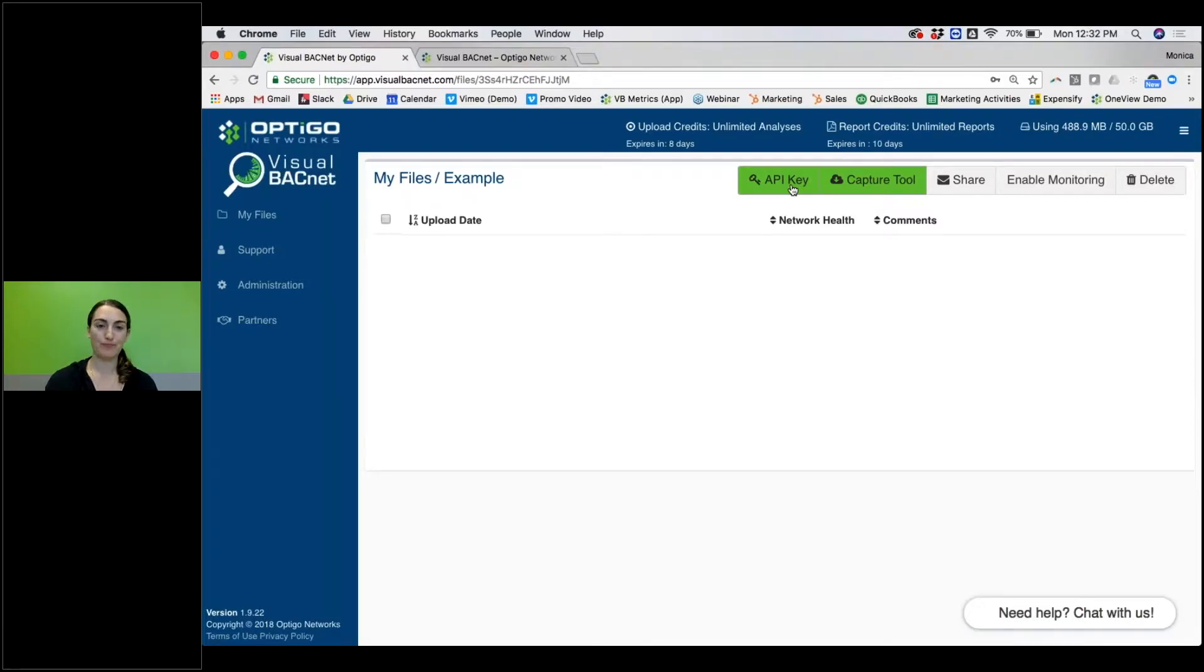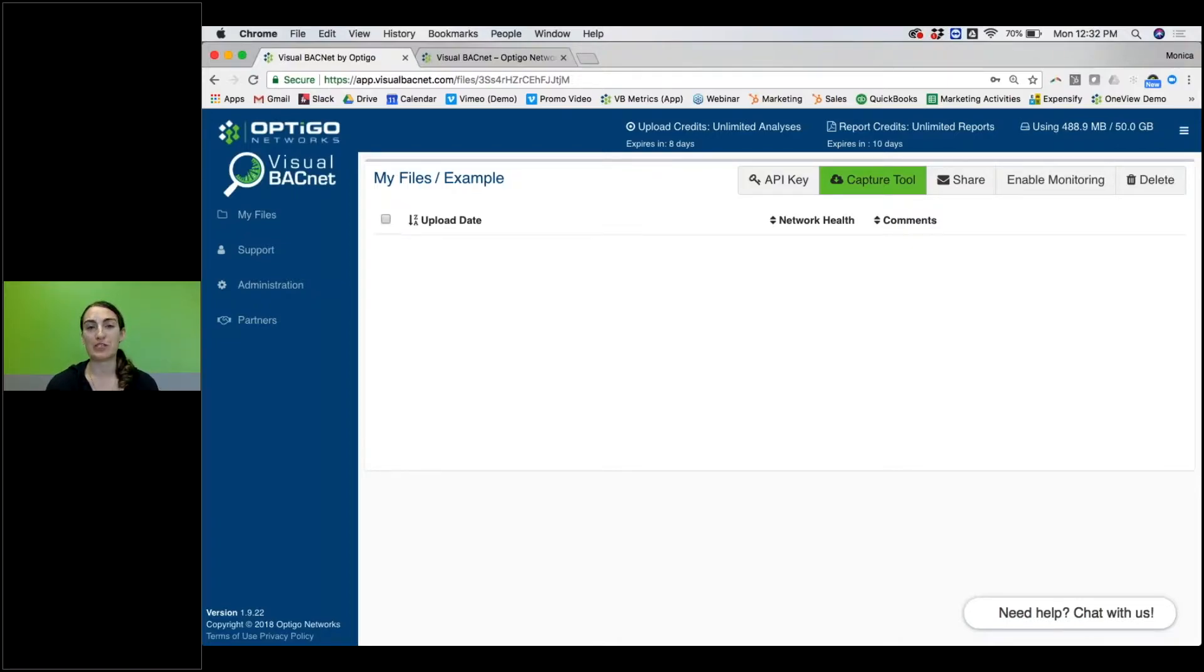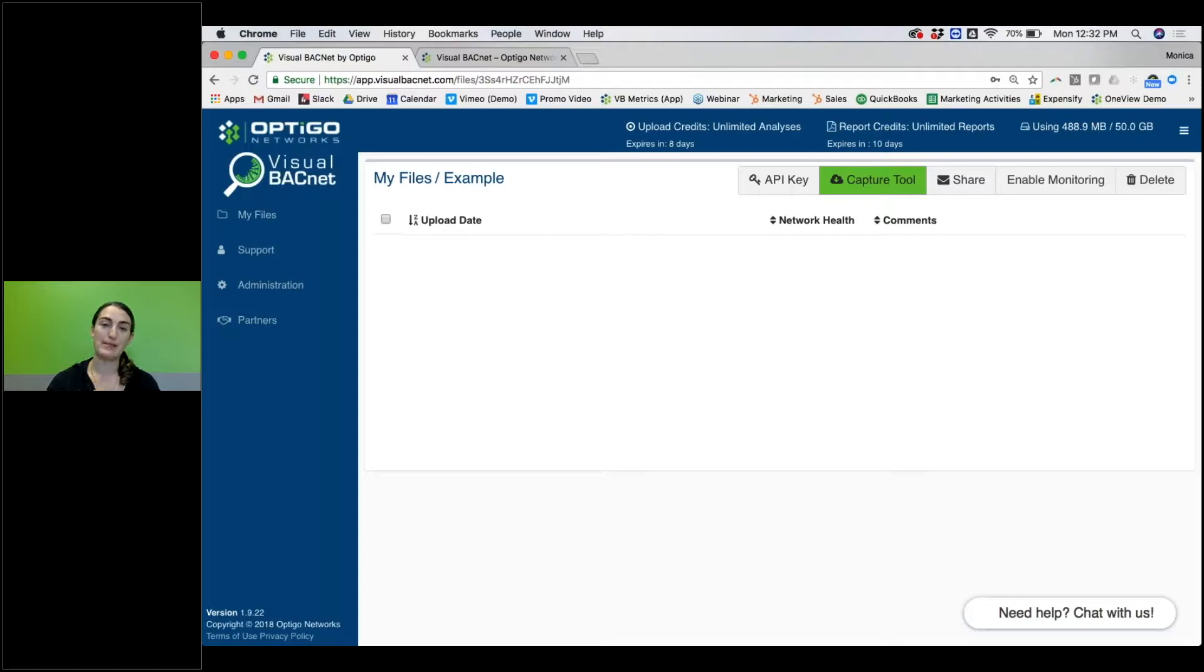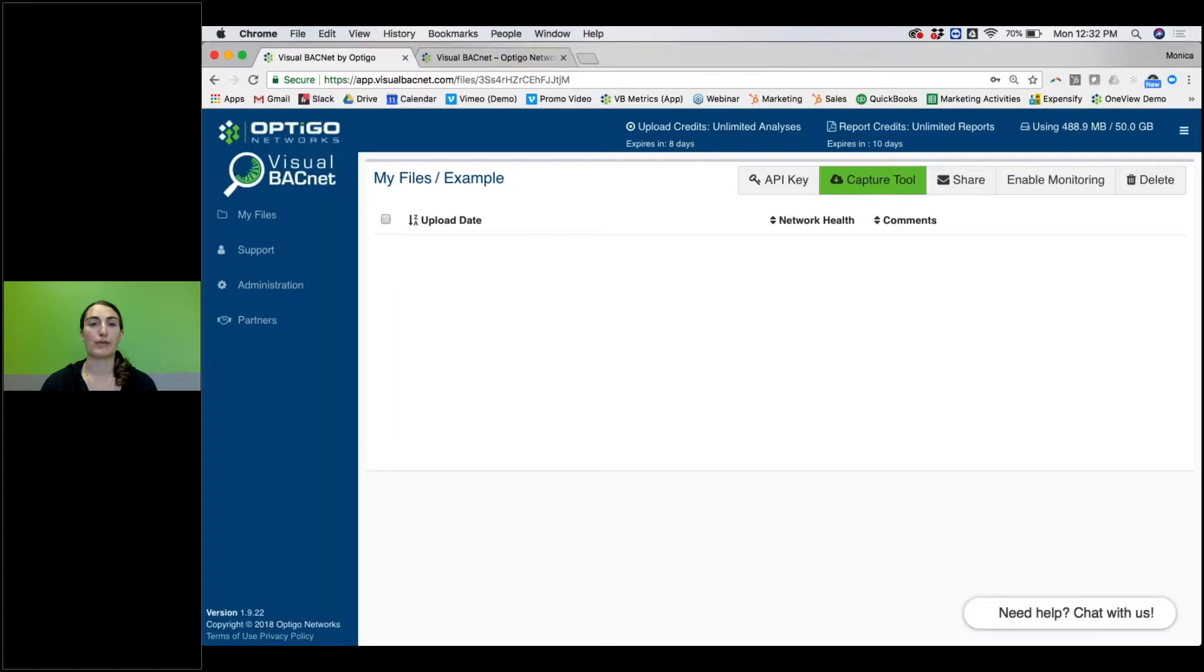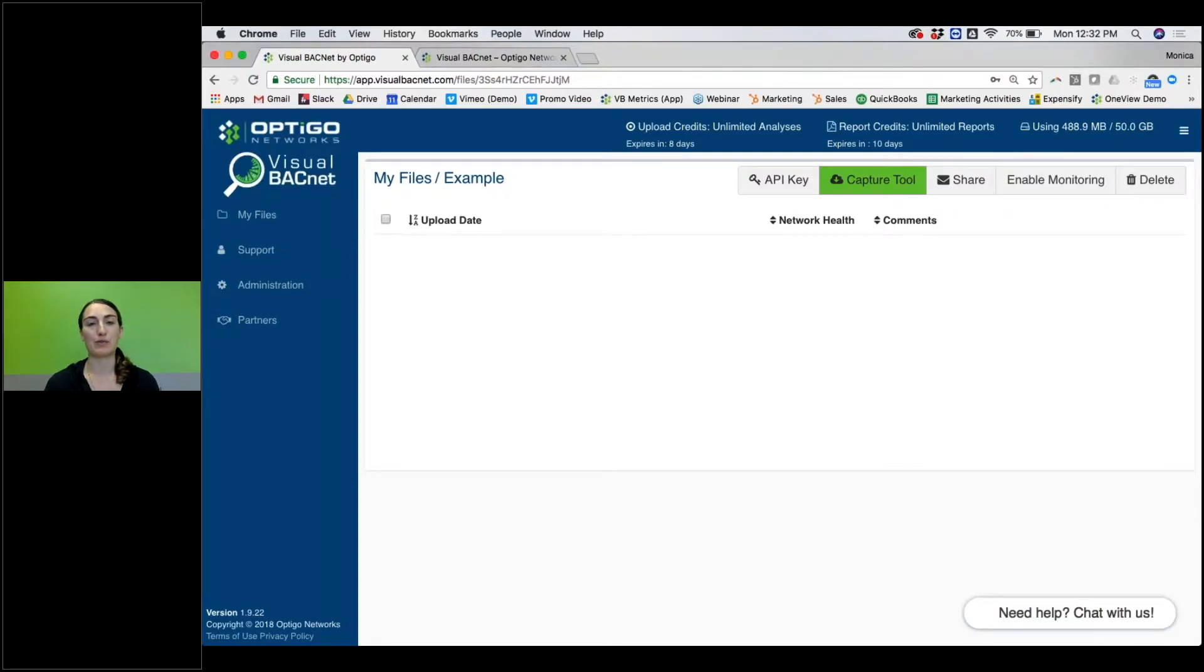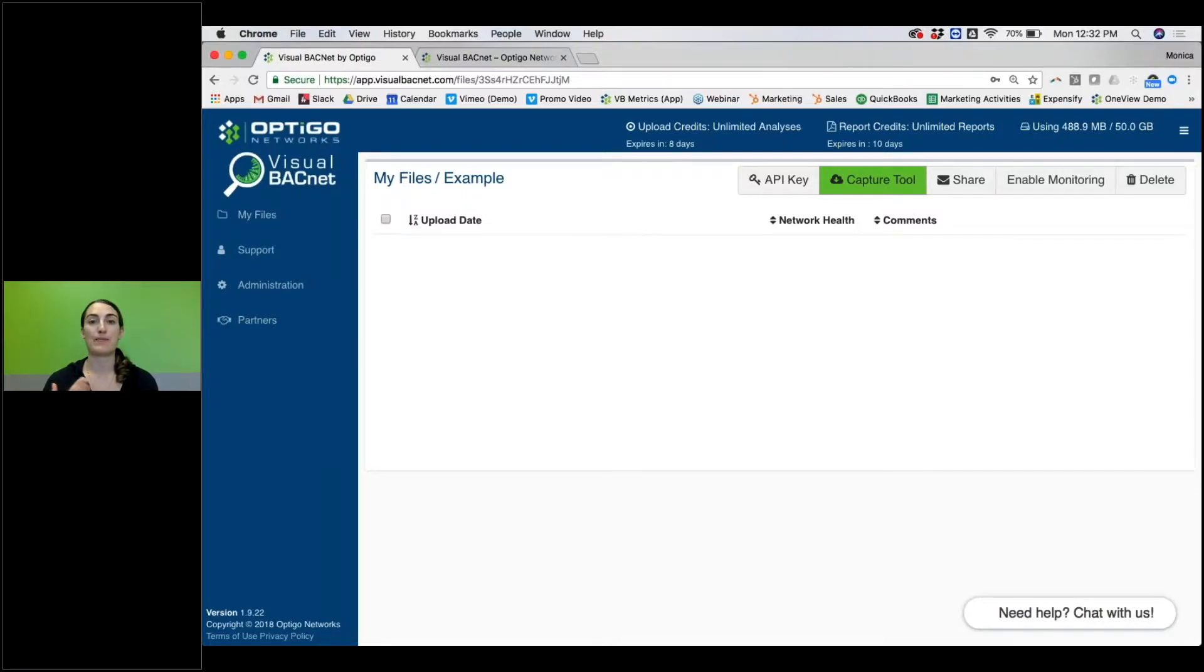Another option: if you are looking to get MSTP data, we have a physical capture tool that you can use, our USB to RS-485 converter wired into your MSTP network. Do the exact same process and have that information from your MSTP chain capture and go up into your Visual BACnet account on a regular basis. Both of those options, MSTP, IP, physical piece of hardware for the capture tool and the Windows capture tool, you can schedule them to capture on a regular basis, so hourly, a couple times a day. It depends how you'd like to configure it, and the information will show up in your account.